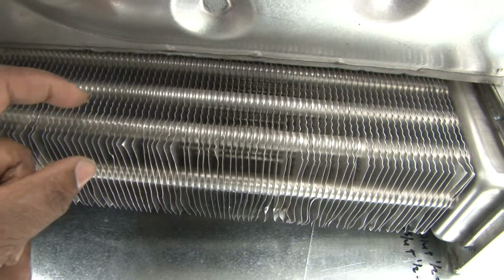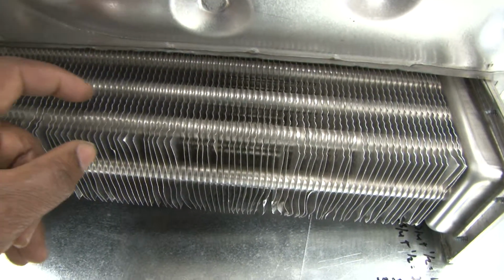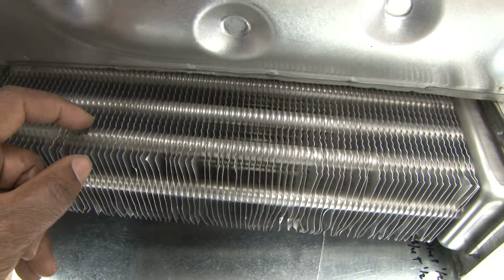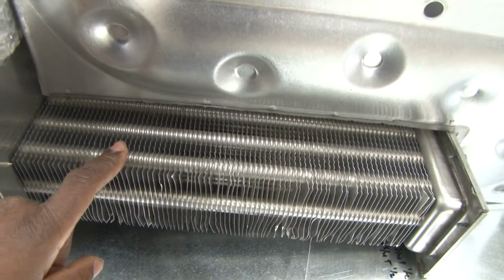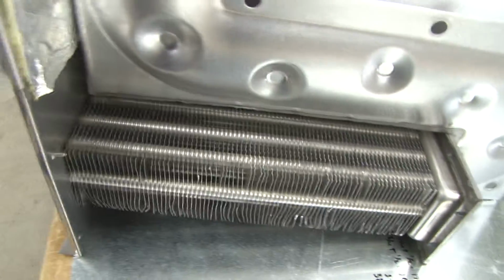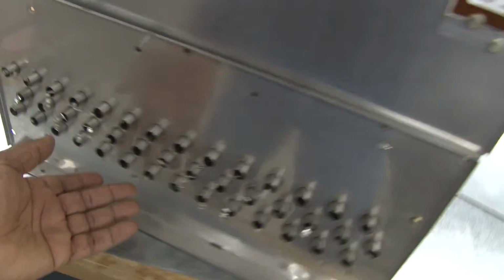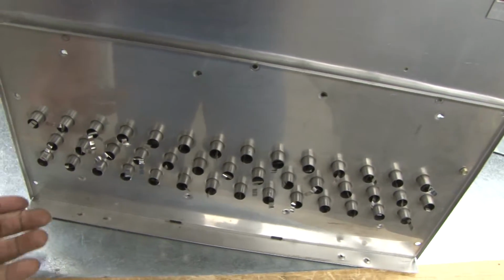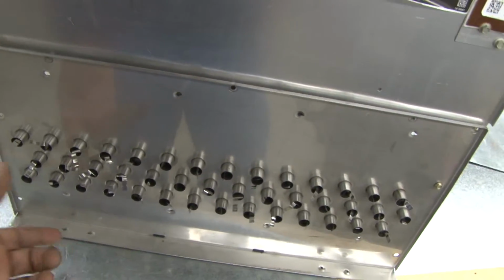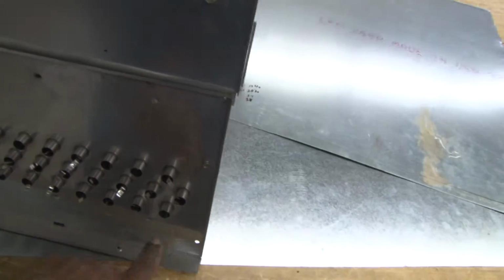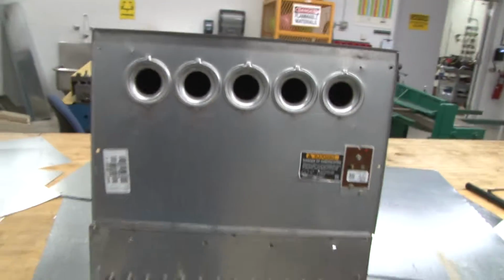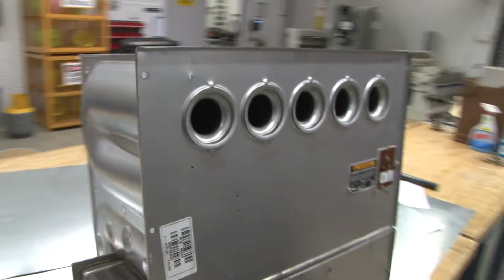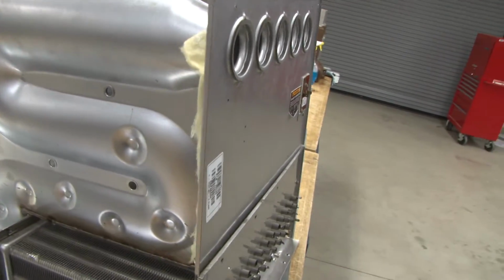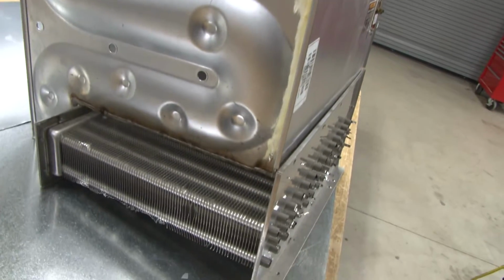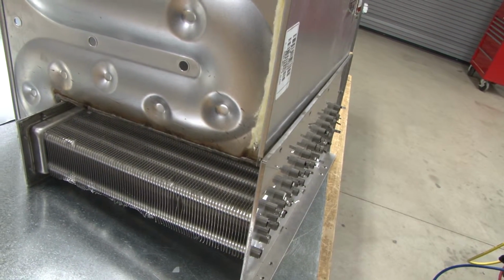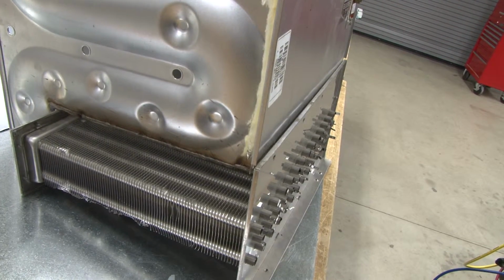So by taking the flue gases, separating them into very small passages, and putting fins on it, it will be able to have a latent heat change, going from a gas to a liquid. Basically, in the very front, as the flue gases come out, they collect inside of a collector box, and the water goes to the bottom and goes to a drain. So basically this is how a high efficiency condensing furnace will operate to make the furnace as efficient as possible.